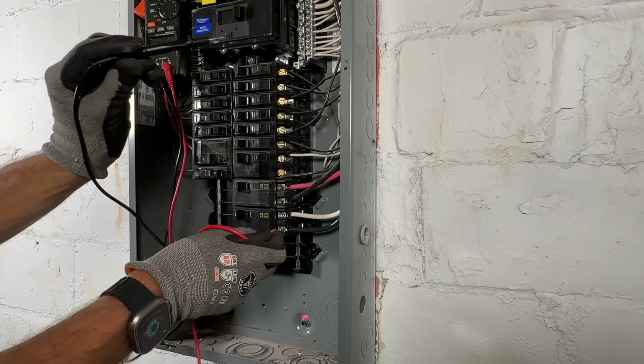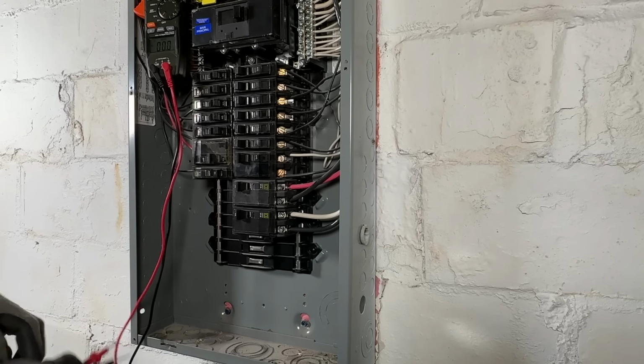We'll go ahead and test the second phase, 119.3, looking good. And then we'll move that black probe and see across the phases, we should see 238. So everything's looking good here at the panel. And now we have our new 50 amp circuit up and running for the AC unit.